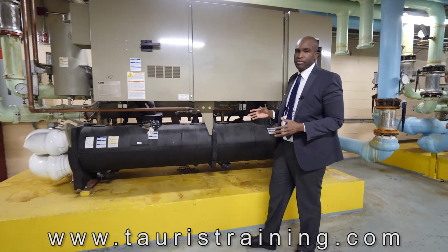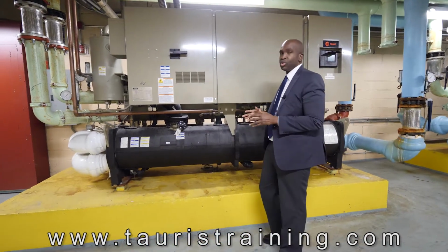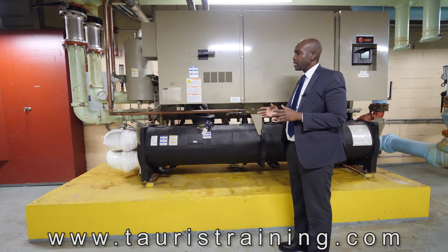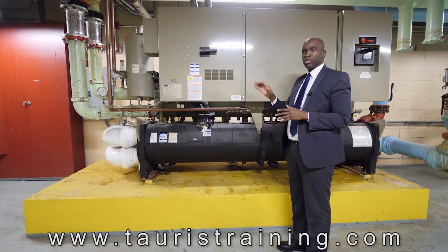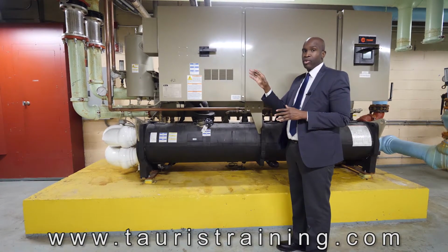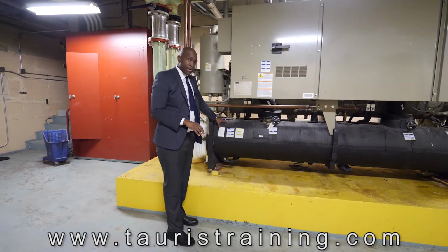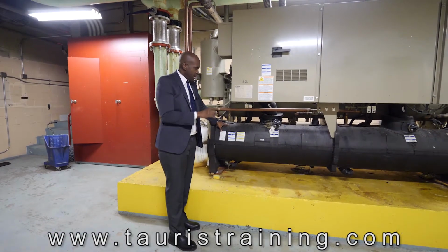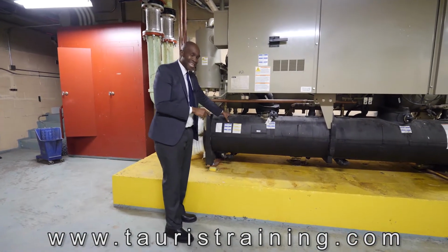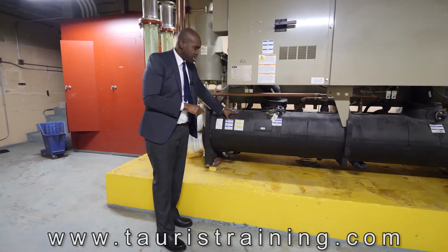This is a chiller. The purpose of a chiller is to produce chilled water. We're basically providing water, usually about 45 degrees, into our building. The chilled water is coming from the evaporator. Now, I know that this is my evaporator because it has insulation on the outside of it.